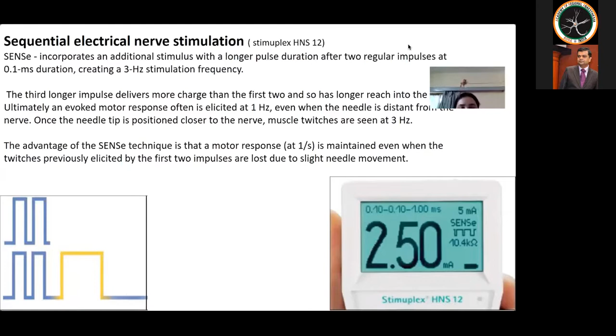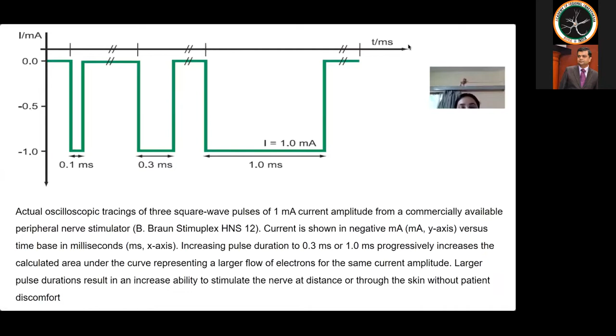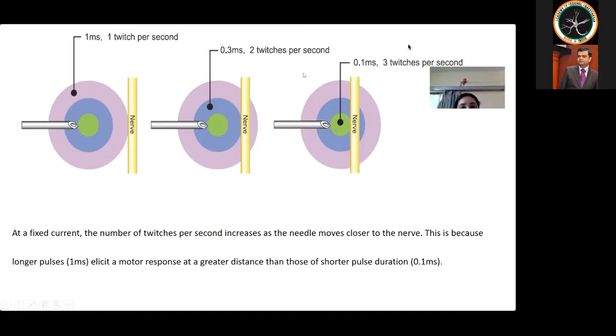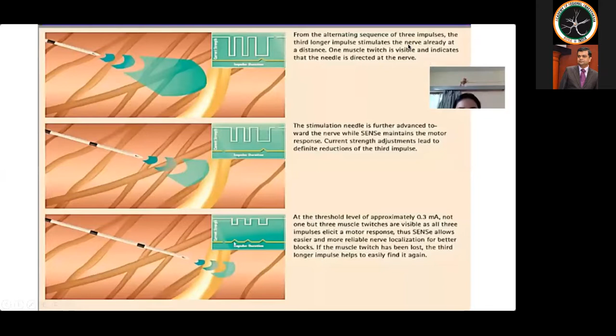So as you can see in the picture, increasing the pulse duration to 0.3 millisecond or 1 millisecond, there is an increase in the calculated area under the curve. That means it represents a larger amount of charge for the same current applied. So the larger pulse durations will result in an increased ability to stimulate the nerve at a distance or through the skin without patient discomfort. Here you can see at a fixed current the number of twitches per second. That is, here is 1 twitch, here 2 twitches, and here 3 twitches per second. This is because the longer stimulus, that is 1 millisecond, produces a motor response at a greater distance than the shorter pulse duration of 0.1 millisecond. So as you can see here, it will produce 3 twitches.